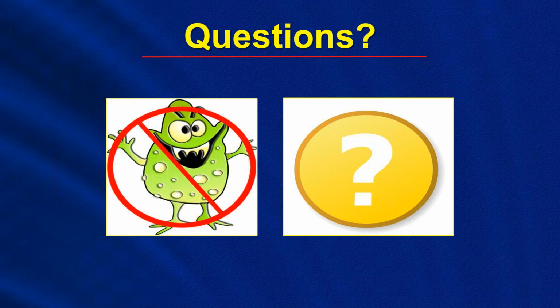Great. So how do we know what germs may be on our surfaces or instruments with ATP testing? Well, you won't know exactly. Using an ATP test, you won't be able to determine exactly what the pathogens or the contamination is, like you would with the cultures in the laboratory or the agar slides, things like that. The ATP is only going to tell you that there's something there. There's ATP, which could be a pathogen, which could be harmful to your patient, which might not be harmful to your patient, but a higher than normal level of ATP just means that it could be cleaner before sending it out for sterilization or high-level disinfection or re-cleaning, such as a surface, like an OR table surface or something like that. Again, it's a measurement of the effectiveness of your cleaning practices, of how well an item or surface was cleaned. So that's what the ATP test does.